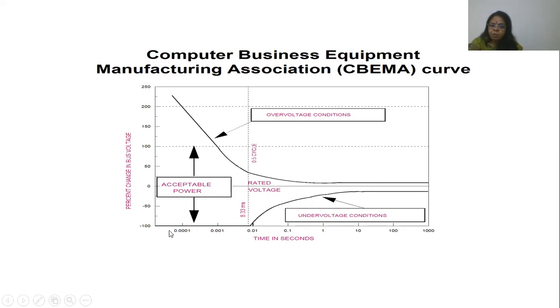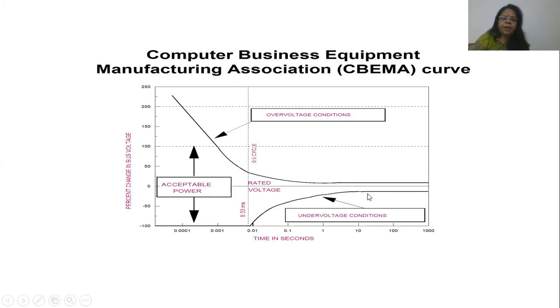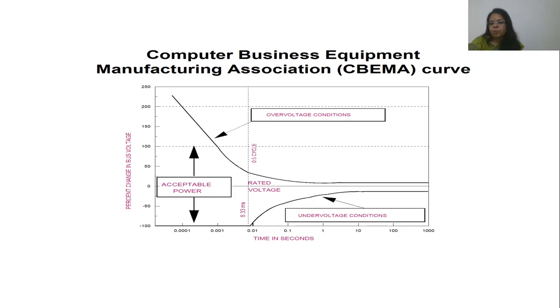The left end of the x-axis shows very short durations; moving right shows longer durations. Two boundaries are drawn — one above nominal and one below nominal. Whatever falls within these two boundaries is acceptable. For example, a 100% deviation lasting only 0.1 millisecond is acceptable — large deviation but very small time. At one second, only a small deviation is acceptable — larger durations require smaller magnitudes.